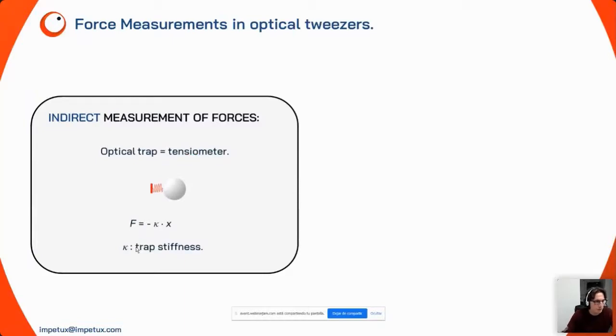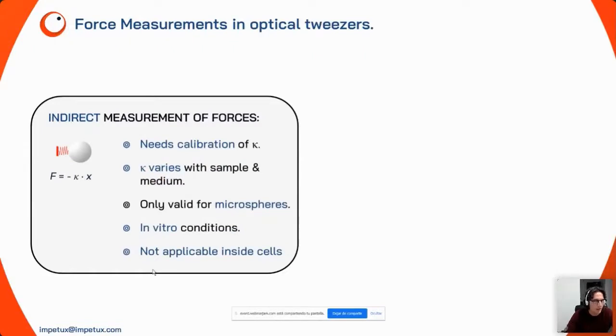To get the force, you need to track the particle position using video tracking or back focal plane interferometry, and you need to know the constant of proportionality kappa, also known as trap stiffness. This requires calibrating the system first. However, kappa varies depending on sample and medium conditions, so if you change experimental conditions you must recalibrate. Furthermore, this indirect method is only valid for spherical objects and is basically limited to in vitro conditions — it cannot be applied inside complex media like cells or tissues.